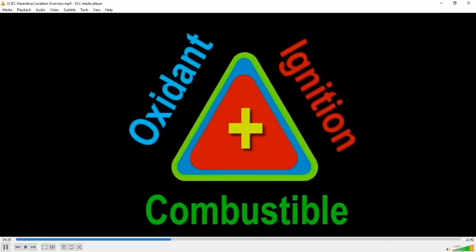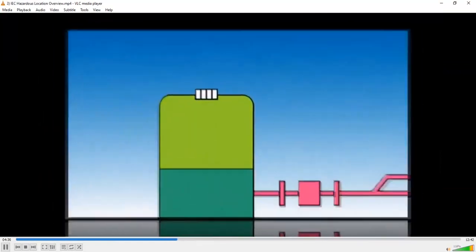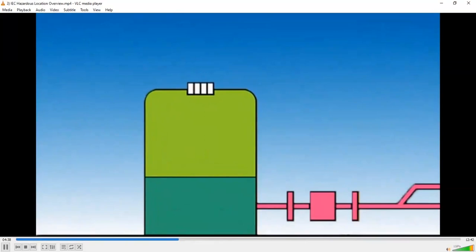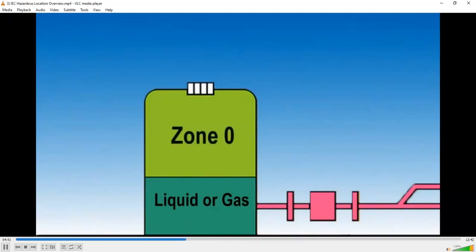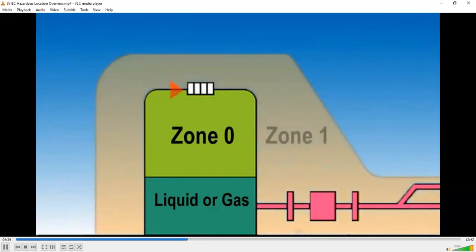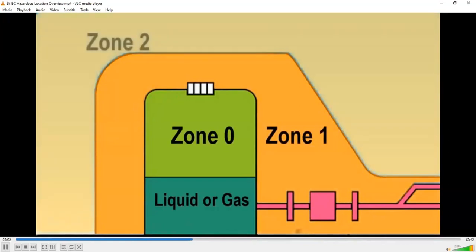Referring back to the necessary requirements for an explosive triangle, we know we need an ignition source, oxygen, gas, and/or dust combustible material in the correct mixture within the atmosphere. In order to specify electrical devices and hazardous locations, we need to identify the general zones within each area. When working with liquids or gas, we locate the most hazardous or flammable location directly above the material. Due to the possibility of the valve leaking at the top of the containment structure, we must classify the area as Zone 1. As we move further away from the possible explosive atmospheric condition, the zone classification would be reduced to Zone 2.